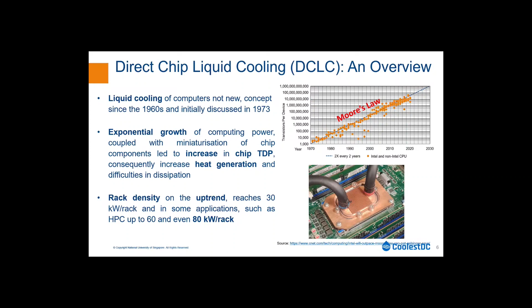If you're in the IT space, you know that associated with multi-core technology, heat flux actually flattened for a number of years. But if you look at what's happened over the last 5 years or so, power density has started increasing again, still obeying Moore's law, which states that the number of electronics components within a certain footprint will double every 18 months. This doubling of electronic components leads to an increase in the heat density that needs to be effectively dissipated. That's why there's now interest in looking into high efficiency liquid cooling.